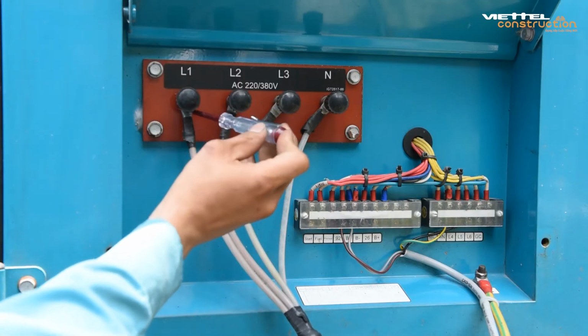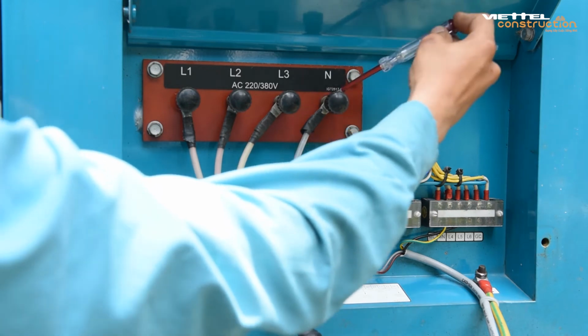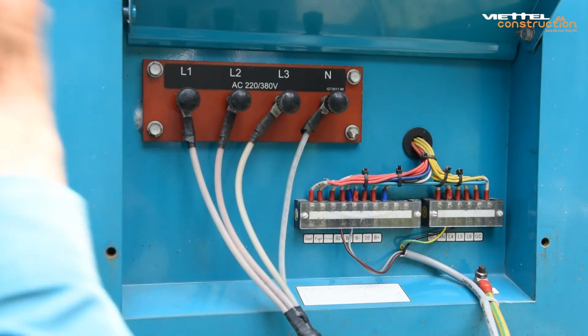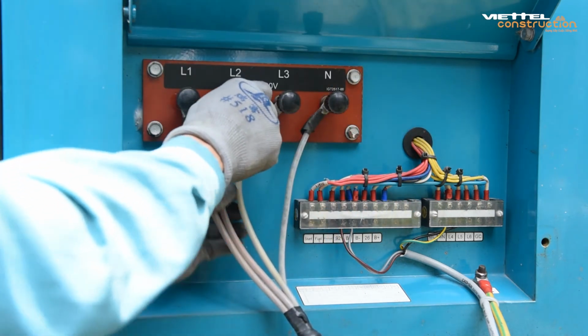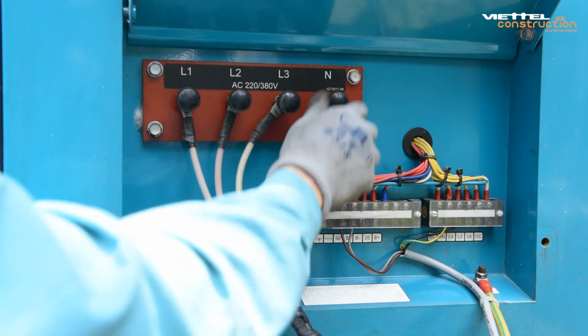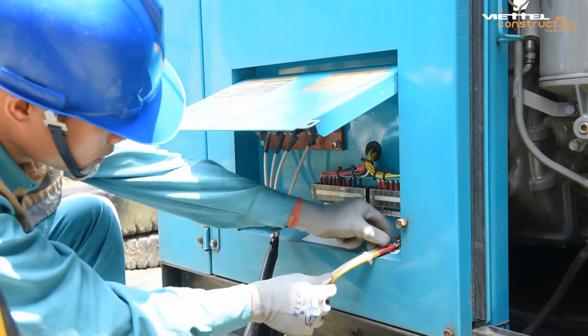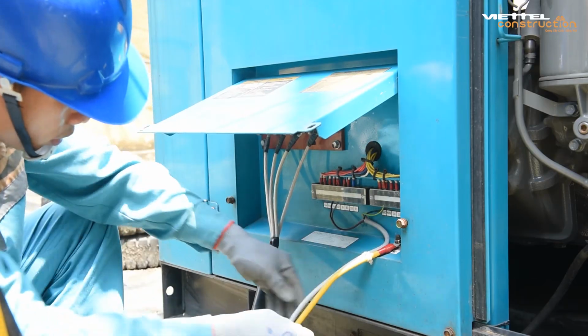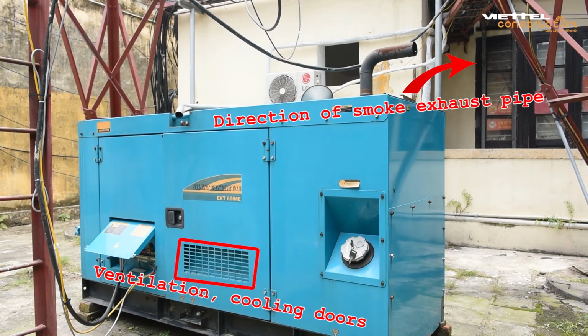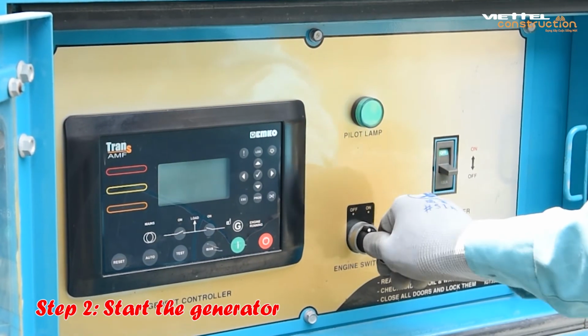Check for electrical leakage at the connection part of the generator. Check the ground wire to make sure it is fixed as prescribed. Check the exhaust pipe to make sure it does not turn in the direction of the cooling vents. Step 2. Start the generator.